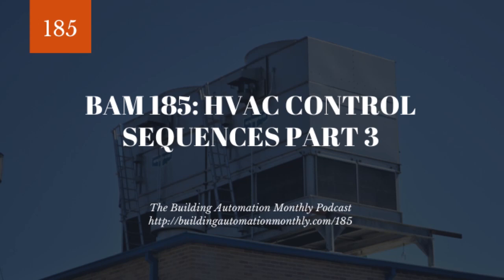So from there, we have our heat, and that's all well and good. We've got heat, we've got cooling, but then we have this thing called ventilation. What is the purpose of that? Well, sometimes you've met your set point. Set point's great, right? You're hitting 65 degree discharge air, you're using economizer, everything's all well and good. But you still need airflow, and that is where ventilation mode comes in. It simply circulates airflow in order to provide airflow to the space as needed, or spaces as needed. So it's important to realize that when you're not in cooling mode and not in heating mode, you still want to have ventilation mode going.